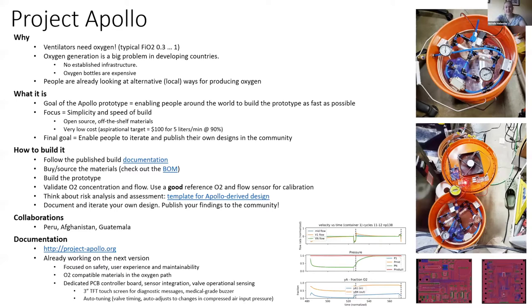What is the fastest flow rate that you have? Five liters per minute is a bit conservative — I think we can get a bit more at the moment. But we really want to get it at 90% oxygen concentration. The whole thing looks like a bucket and appears inexpensive, but you can actually put multiple devices in parallel and just scale out production by adding more devices.